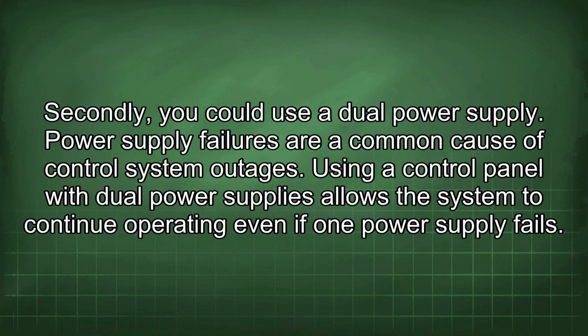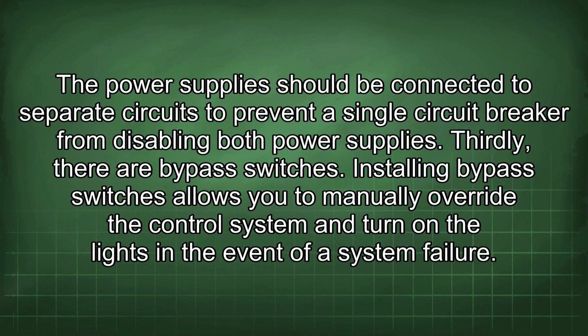Secondly, you could use a dual power supply. Power supply failures are a common cause of control system outages. Using a control panel with dual power supplies allows the system to continue operating even if one power supply fails. The power supplies should be connected to separate circuits to prevent a single circuit breaker from disabling both power supplies.